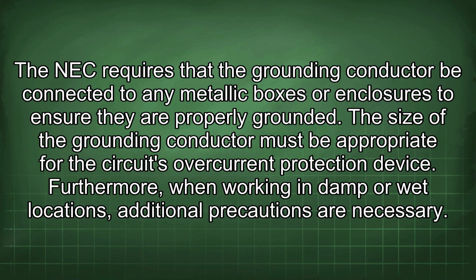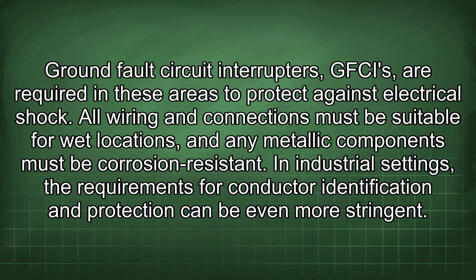Furthermore, when working in damp or wet locations, additional precautions are necessary. Ground fault circuit interrupters (GFCIs) are required in these areas to protect against electrical shock. All wiring and connections must be suitable for wet locations, and any metallic components must be corrosion resistant.